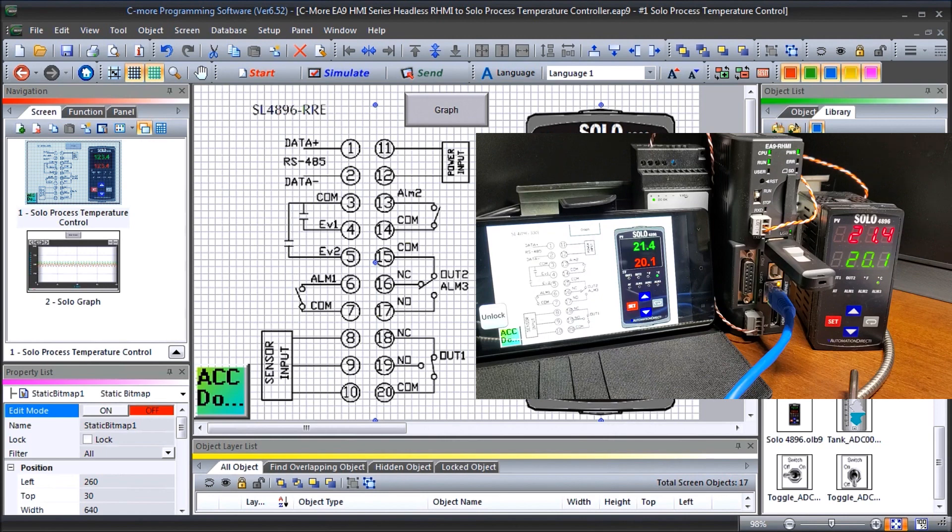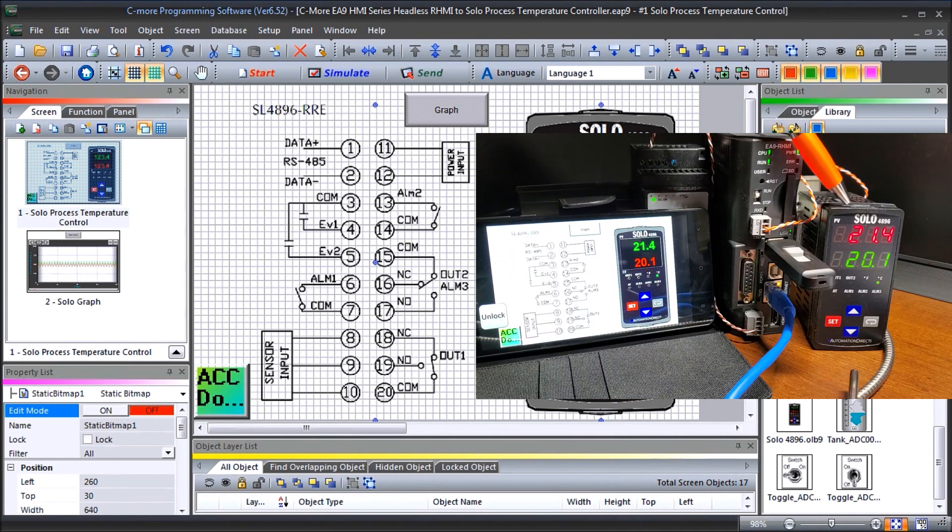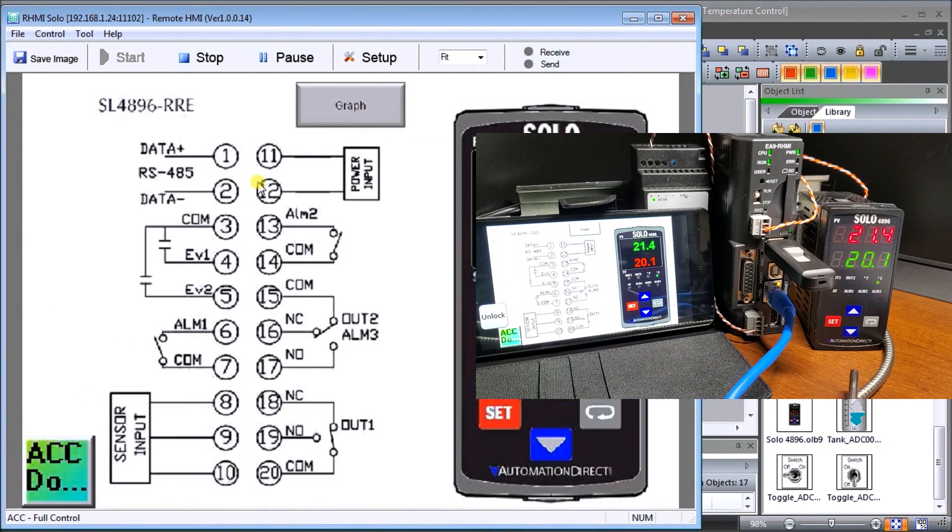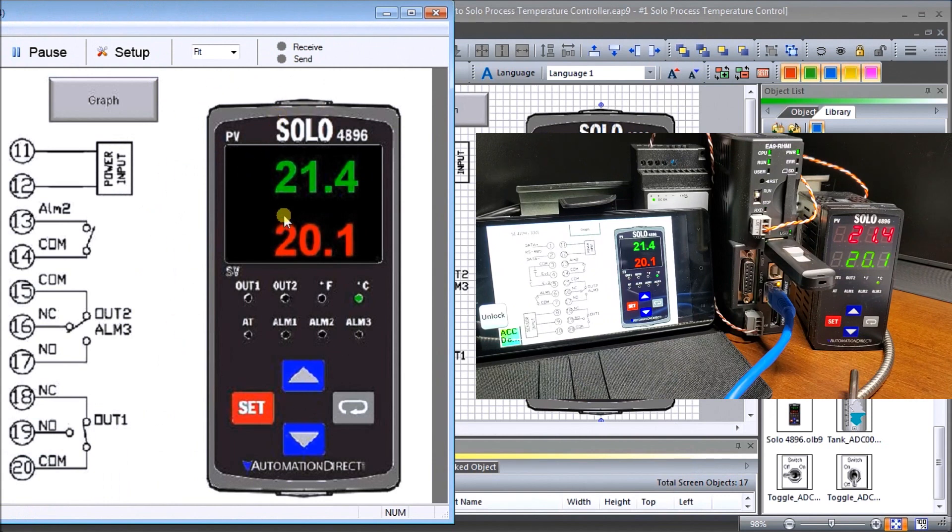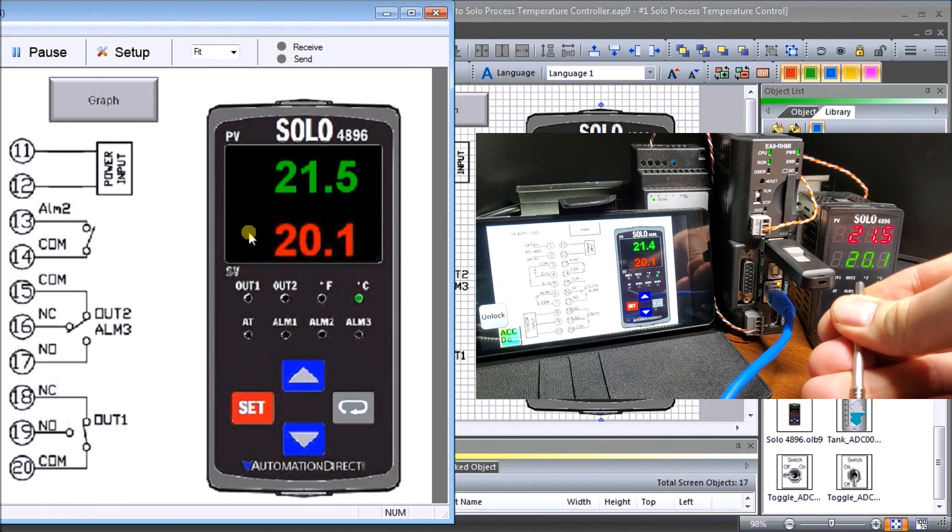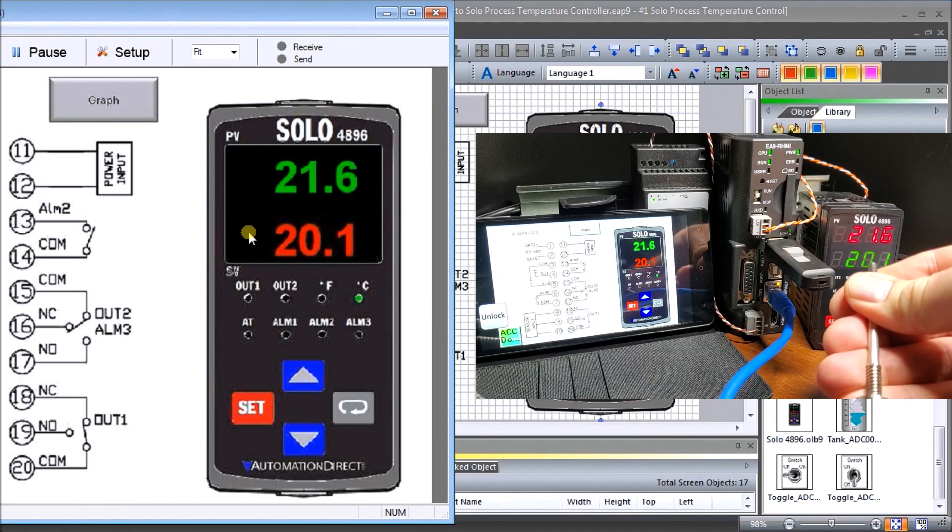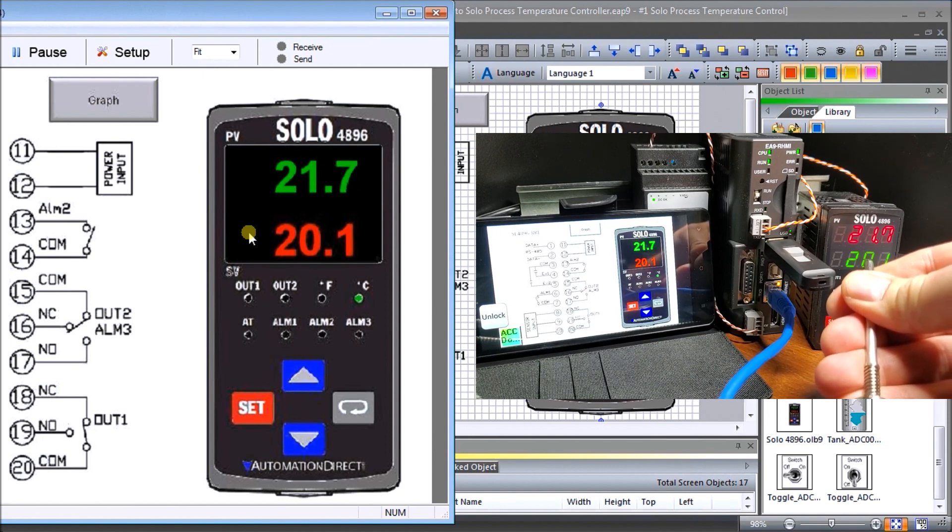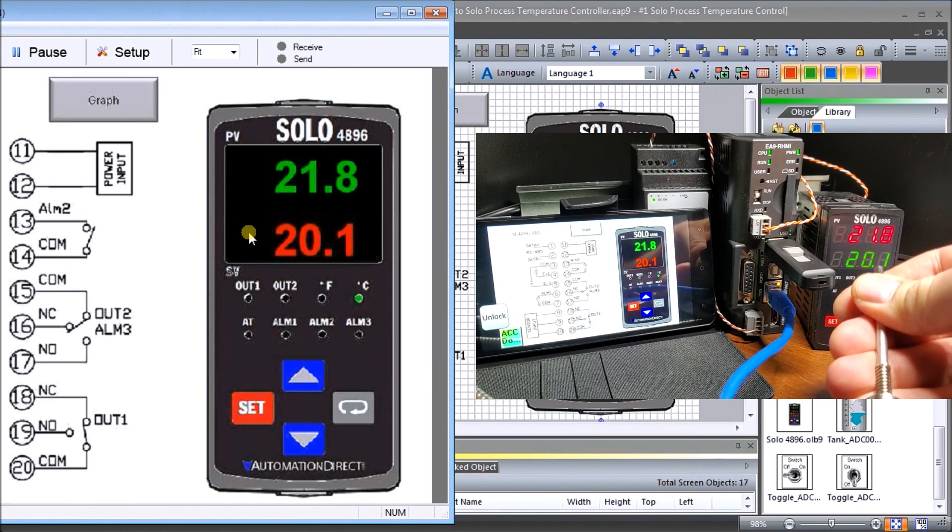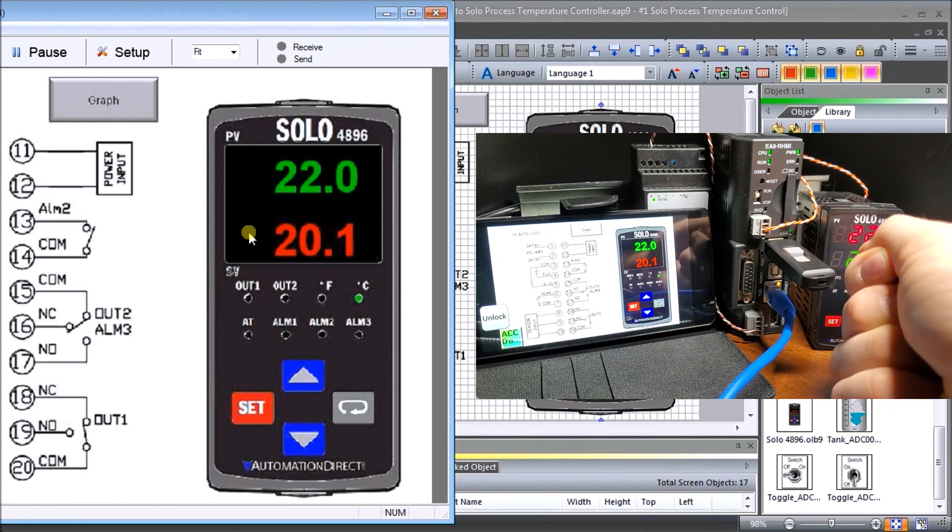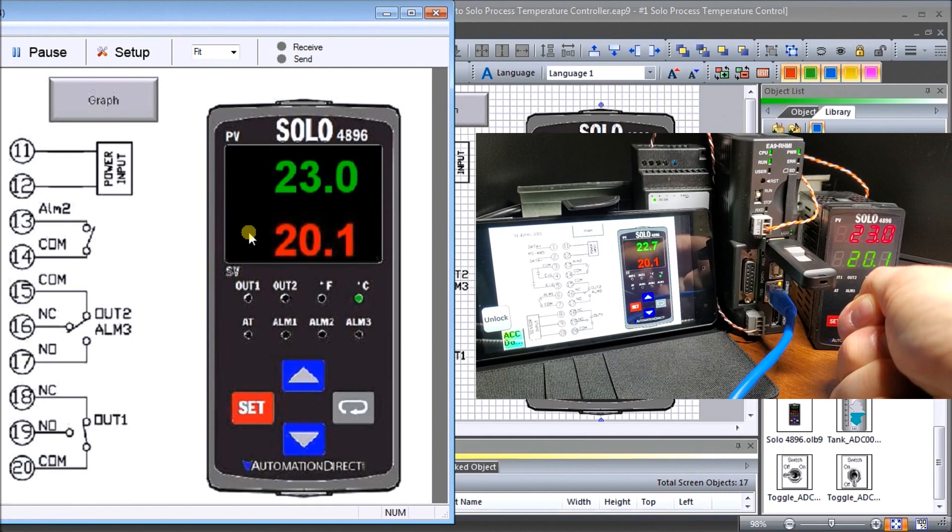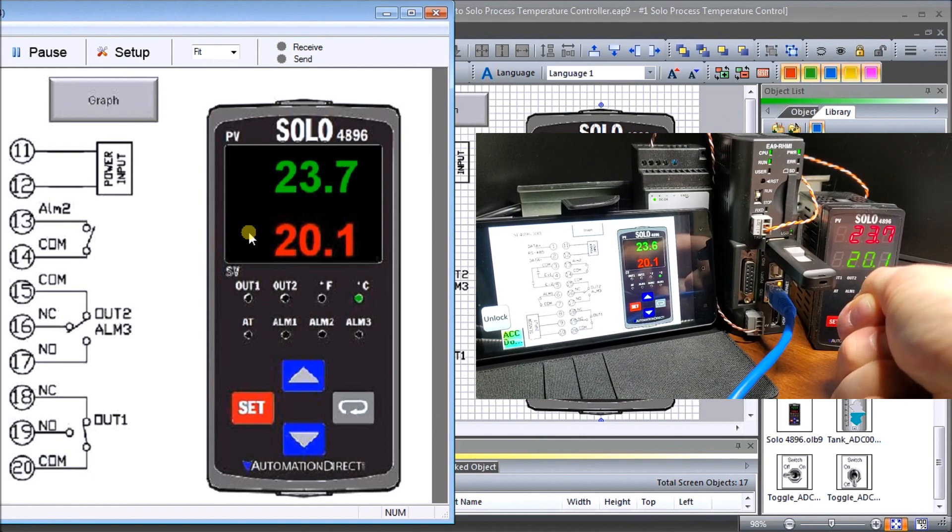I also have beside here is the android app open and running which is actually communicating and showing the value that we have here. And what we can do is also at the same time we can look at our windows application and the windows application again looks like this. I'll move it over a little bit and here we go here and there's our solo process controller with the values that we're seeing. So what I'll do is hold on to my thermocouple and as I hold on to my thermocouple the present value will then start changing and you can see that the changes are reflected both on our windows remote access as well as our android remote access that we're displaying. And I'll just hold on to it tightly and you can see that we can rapidly ramp it up. So it's just showing you the values.